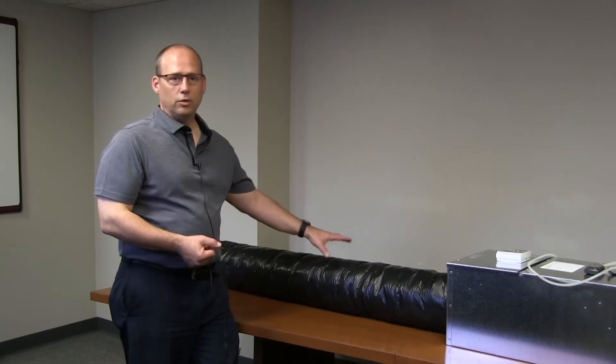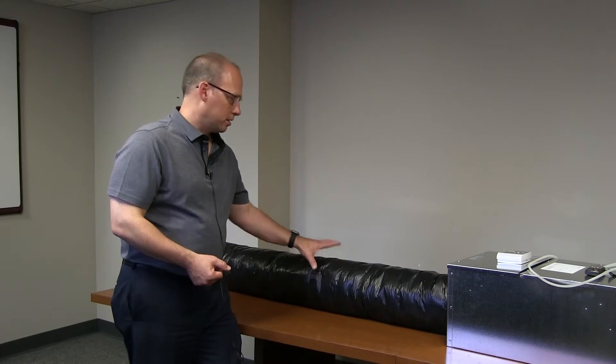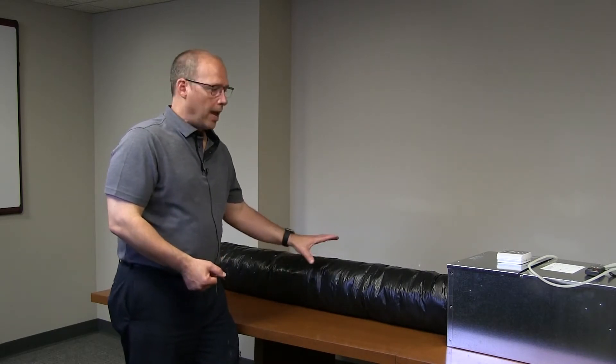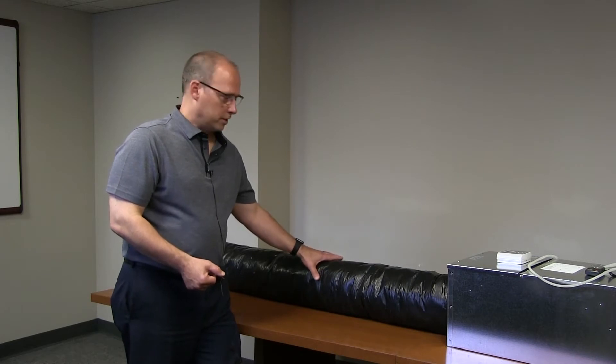So if you don't take the measurement at the inlet hood, the other thing that the ResNet 380 standard allows is for you to take a mid-duct measurement. There's a couple ways to do this. Number one, the standard says to use an airflow station. That really requires that you have a hard piece of sheet metal somewhere in your duct system. This system is flex duct, as most are, and it's not always convenient to put an airflow station.